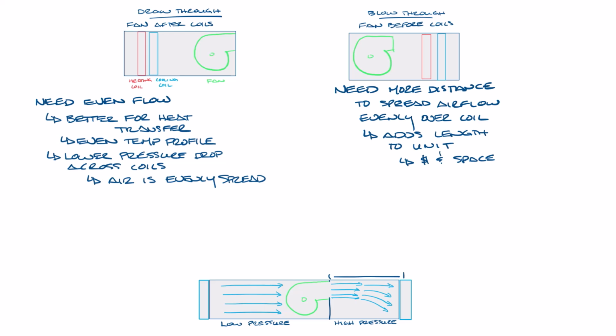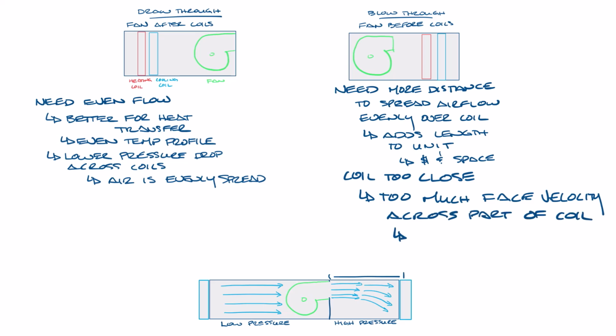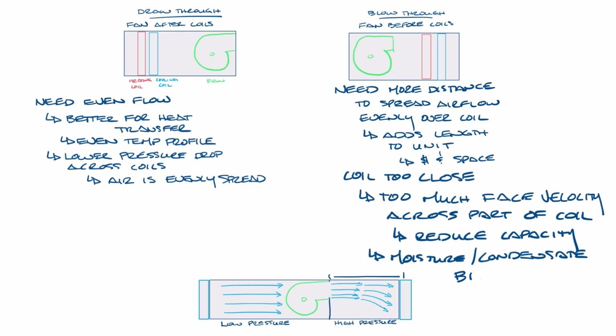If the coil is too close to the discharge of the fan, you could have too much face velocity in the area of the water coil that the air is passing through, and that can reduce the capacity of your coil because you're underutilizing the other areas of the coil. It can also cause moisture or condensate blow-off. This is when water droplets are blown off the coil into the airstream, and you don't want this to happen. For these reasons, draw-through is the most common arrangement for air handlers.